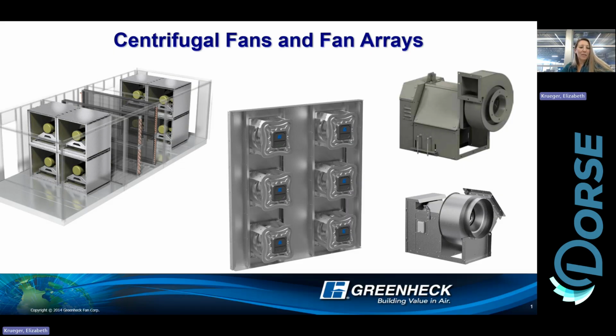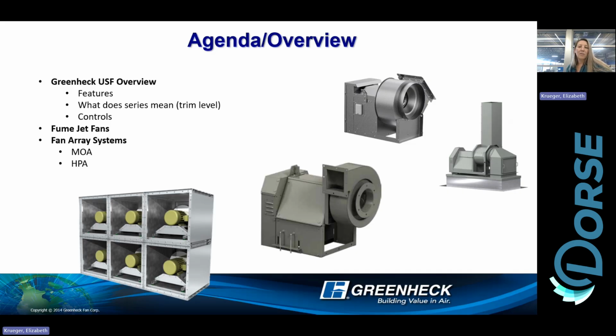We'll talk about our USF, our utility set fan, that's our blower fan. The fume jet is actually a component to that. It's like a next step up, where we have a blower with a stack. Beyond that, we'll go into fan array systems. All of these fans use a centrifugal style wheel and have an inlet cone, so there's only one direction that air can flow with these style fans.